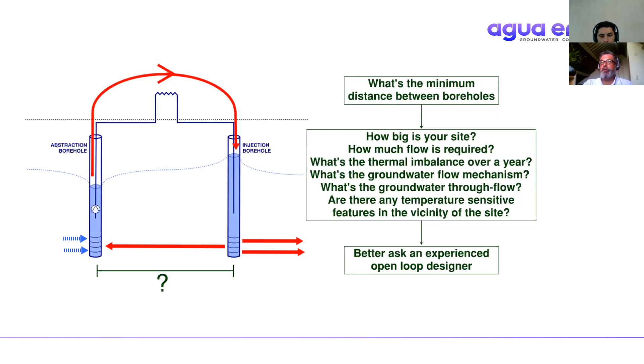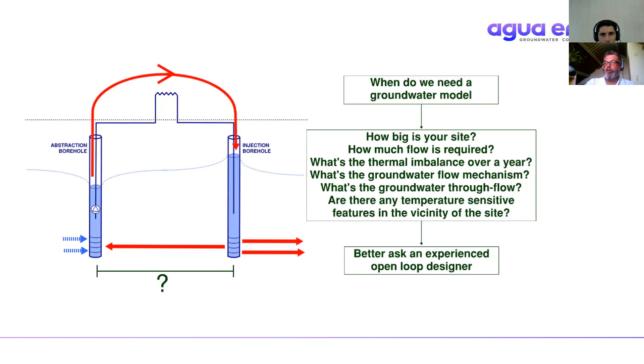So, when do I need a groundwater model? Again, you better ask an experienced open loop groundwater heat pump designer. We don't always need a model, but certainly to de-risk the project and progress in a sensible manner, an open loop system should be under the guidance, or at least the oversight, of an experienced designer.